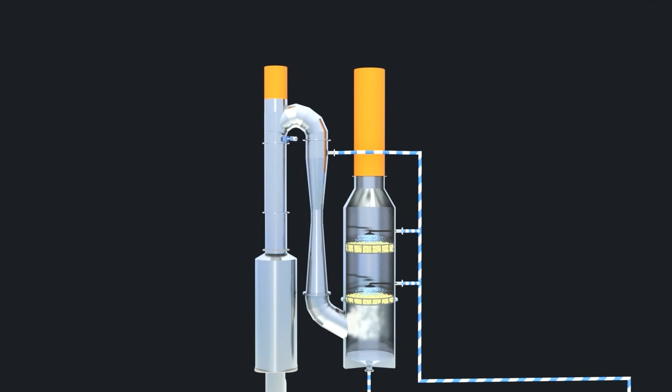Inside the scrubber unit, scrubbing water is sprayed downwards through packed beds in two stages, eventually coming into contact with the exhaust gas coming from below. Packed beds improve the mixing of the exhaust gas and water and increase the surface area available for the SOx scrubbing.